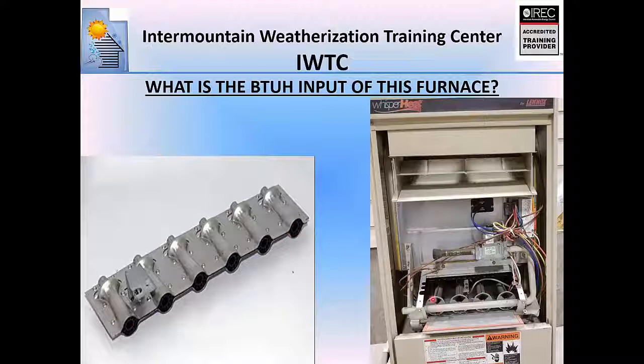Now, this one over here is different. This one is 25,000 BTUs per burner. So if I got 4 burners in there, what's my total BTU input? 4 times 25,000 is 100,000, okay? And if I were to look at the tag on this one, that's what it would tell me. So your burners, if you don't know what the BTU input is, count the burners times 20,000, and that will get you really close. Just remember, there are some oddball ones out there that will do 23,000 per burner, and some that will be 25,000 per burner. But if you use that little rule of thumb, it will get you close enough to know what it is.